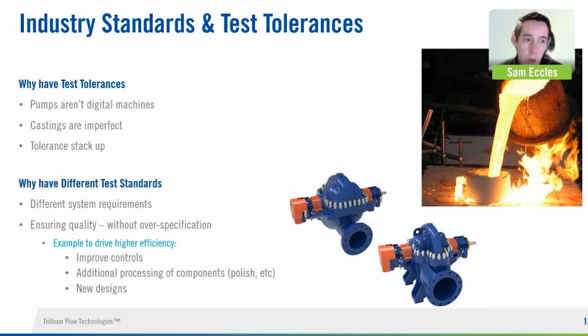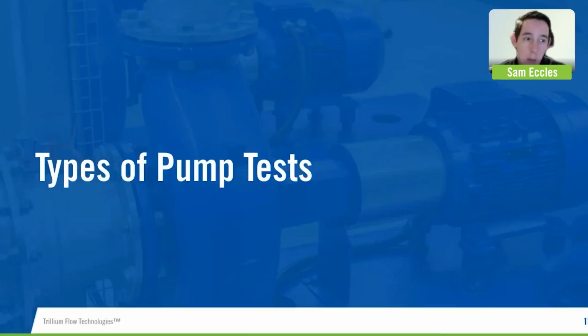That variation is normal. There are a lot of things that we can do as a pump OEM to reduce that variation, and we'll talk about some of those later. But this is why we need different test standards, because reducing that variation adds cost and more and further checks to the system. We want to make sure we're only doing that where it's appropriate and correct. So, for example, if we were trying to drive higher efficiency, we could put tighter controls on inspection, we could polish components, but ultimately it may force us down the road of a new design. So the test standards that are picked are of critical importance.